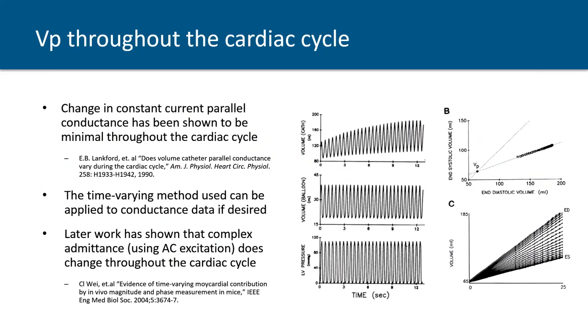And they've regressed each of those isochrones back, as you can see in the bottom corner there. Theoretically, they should all regress and intersect at a common point, again being the parallel conductance. The reason this was done was, one, to assess how robust the technique was instead of just looking at two points in the cardiac cycle. Now you looked at multiple points, and this verifies that you've done a good saline calibration. But it also, more importantly, assesses if the parallel conductance is changing throughout the cardiac cycle. And if it is changing, then each of those regressions will not converge to a single point.